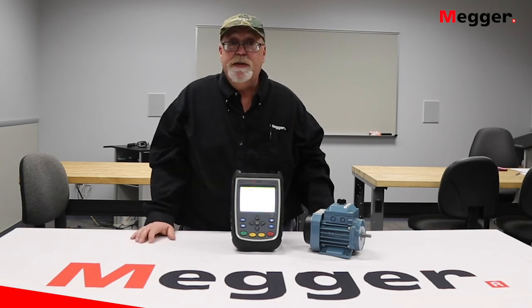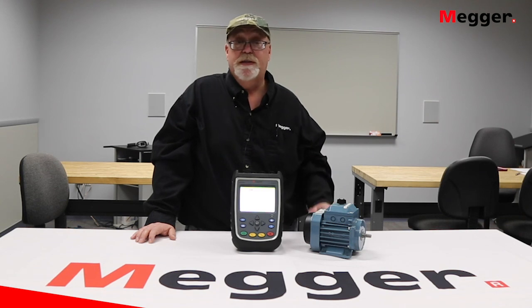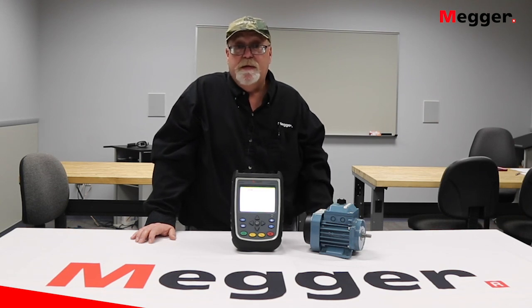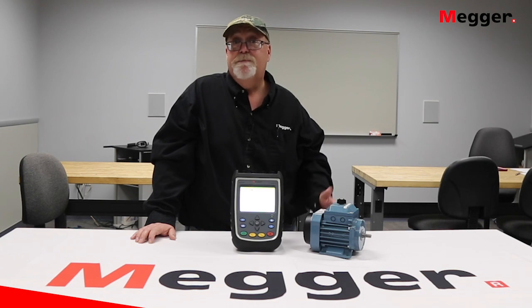And when you get these voltage dips, these can cause issues in the plant, such as lights dimming, loads tripping out, disruption of sensitive equipment, and protection devices. A large enough voltage dip can actually keep the motor itself from starting.